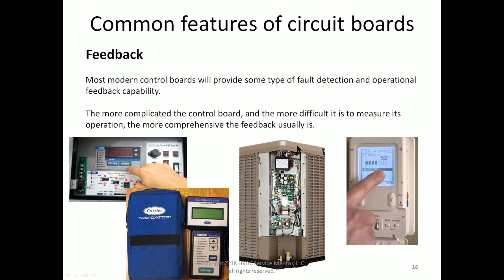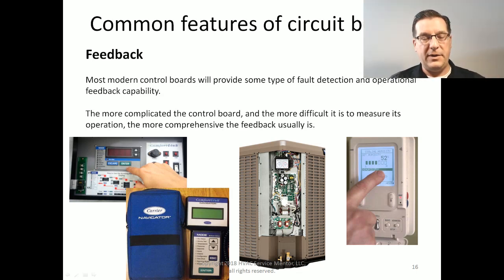The more complicated they are, the more difficult it is to measure their operation, the more comprehensive the feedback usually is. Here's an example. This is a very sophisticated, right here in the middle, modulating variable capacity heat pump or air conditioner, and it has an actual touch screen controller in it. It measures refrigerant pressures. It gives all kinds of diagnostic feedback. This whole thing is just a mass of electronic controls, and you have absolutely no way of working on it without this user interface. Same thing over here on this older, sophisticated Lennox communicating control. This thing is required for diagnostic feedback. And in the commercial world, we have a similar thing where we can have an actual plug-in device for this Carrier system that's going to give us all kinds of diagnostic feedback information. So don't lose hope. The more sophisticated things are, the more sophisticated your diagnostic feedback is going to be, and that can just make troubleshooting sometimes easier.